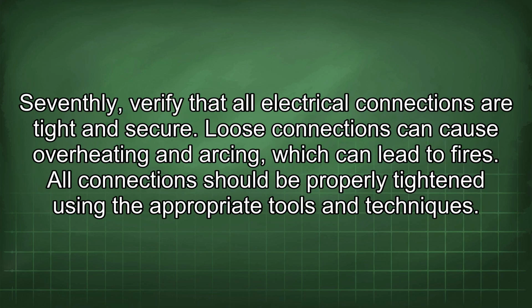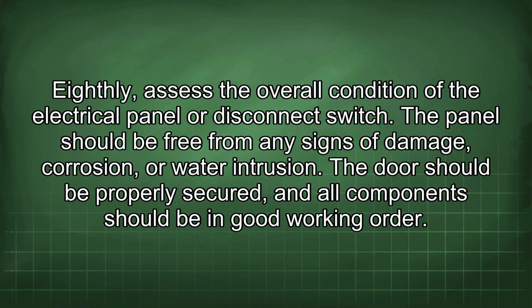Seventhly, verify that all electrical connections are tight and secure. Loose connections can cause overheating and arcing, which can lead to fires. All connections should be properly tightened using the appropriate tools and techniques. Eighthly, assess the overall condition of the electrical panel or disconnect switch. The panel should be free from any signs of damage, corrosion, or water intrusion. The door should be properly secured, and all components should be in good working order.